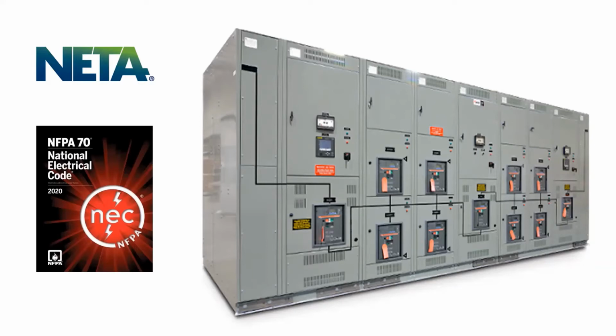Thank you, Adam. They'll set up the breakers, test them, and it's pretty cool to watch. I've seen them bench test breakers, injecting them with current and forcing them to trip. They'll do all your settings from the engineer, your trip settings, because out in the field, when in doubt, people just crank it all the way up, right? It'll never trip, bad idea, agreed? So you're going to receive your gear totally set up and in perfect operating condition.